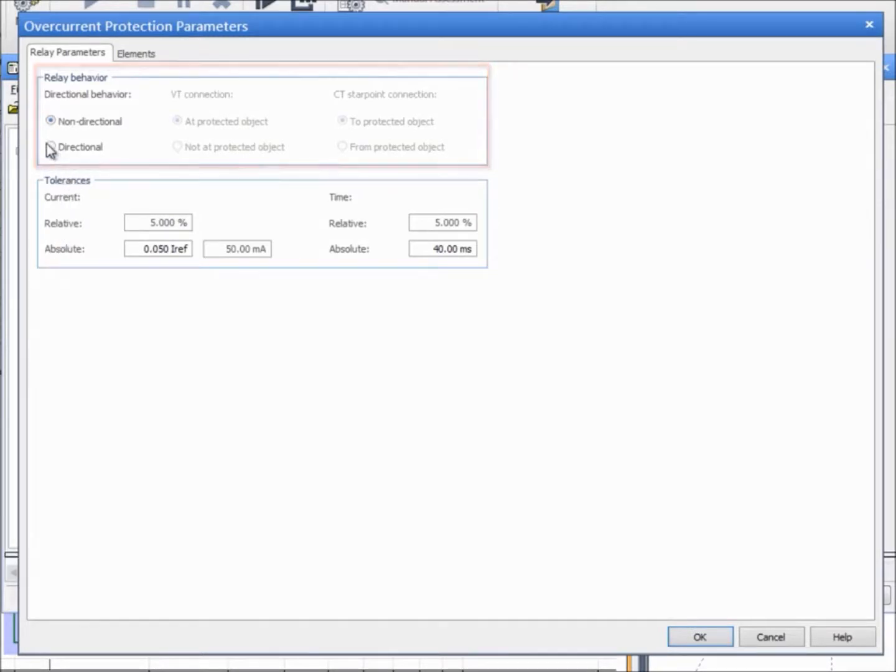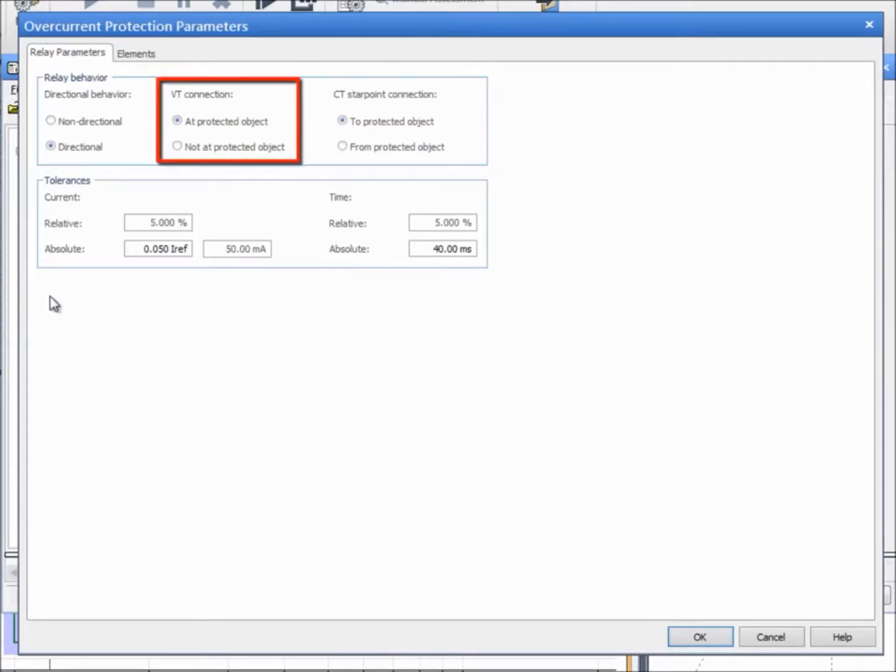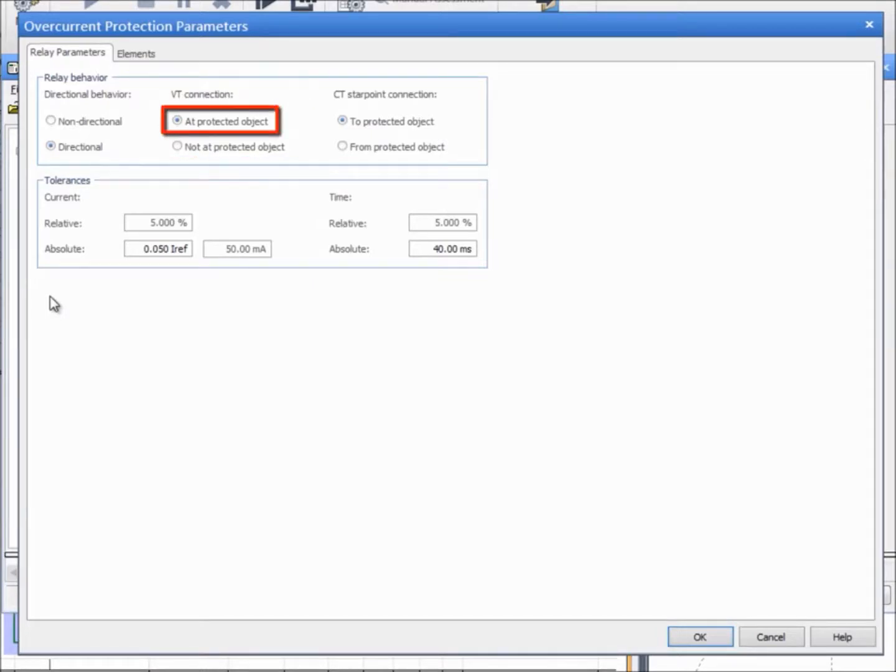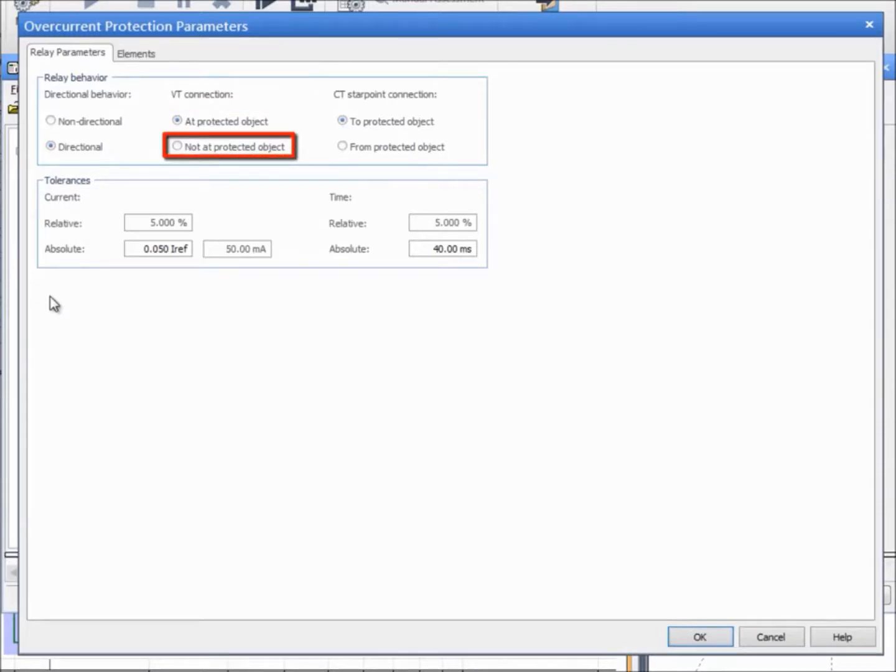When directional is selected, the options for VT and CT connections are enabled. The VT can be installed before or after the circuit breaker. Select At Protected Object when the VT is installed after the circuit breaker. Select Not At Protected Object when the VT is installed before the circuit breaker.